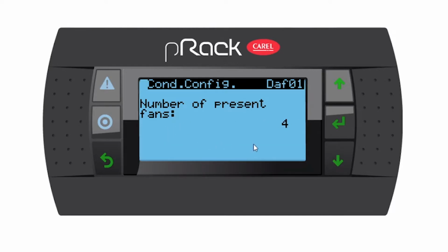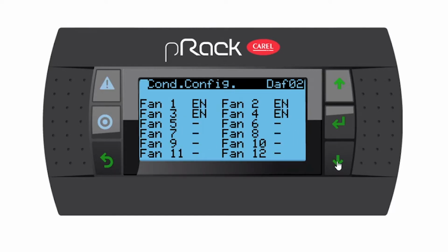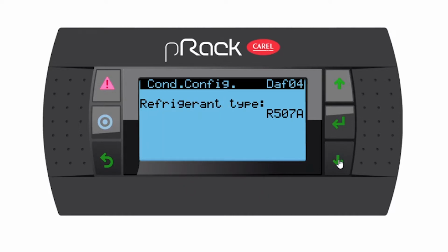Number of fans present is 4. If we go down, here you can see all 4 fans are enabled. Remember, you have the option to disable a fan when it's maybe faulty, but I'm going to leave all 4 enabled and go down. Refrigerant type is 507, perfect.